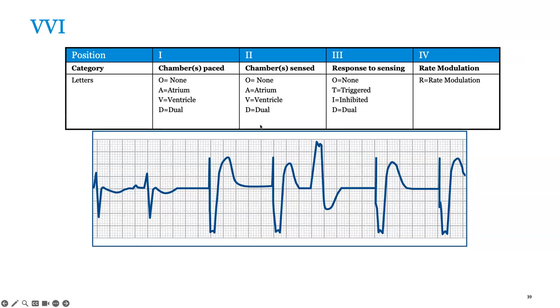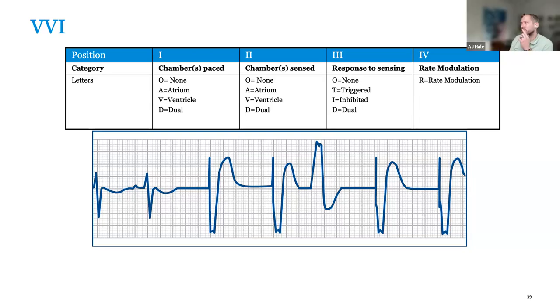Medtronic CRTs have a V-sense response which should always be on — that's kind of a form of VVT that triggers on ventricular events. It paces even in conducted AFib, trying to maximize pacing percentage to improve resynchronization of the heart. You can go in and change those settings including the rate at which you want it to trigger.